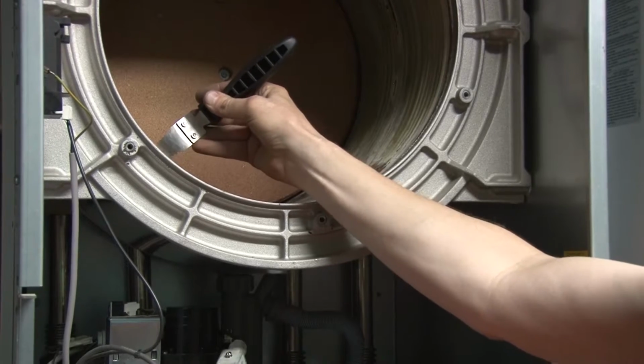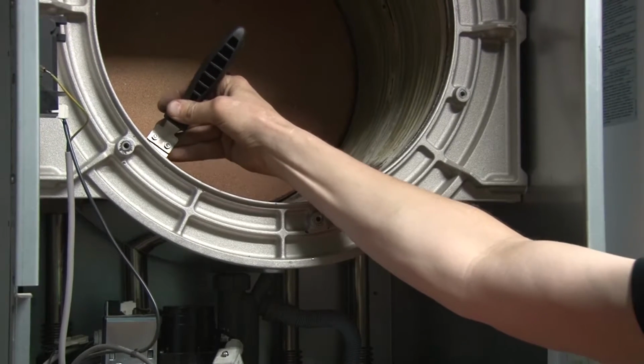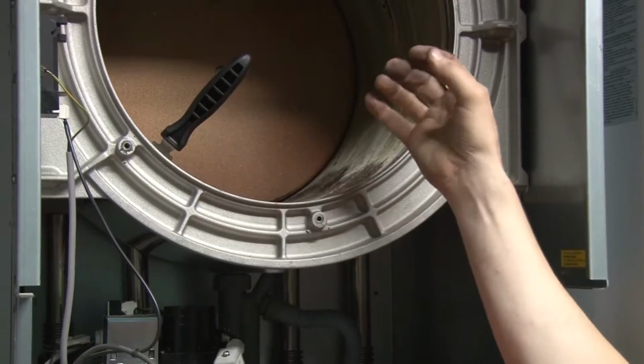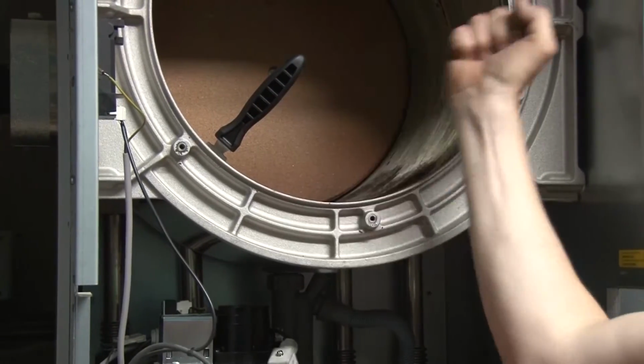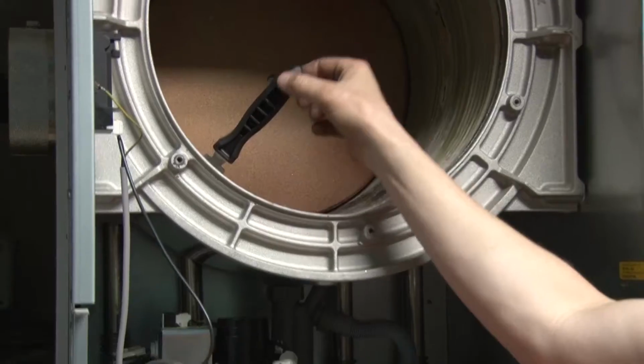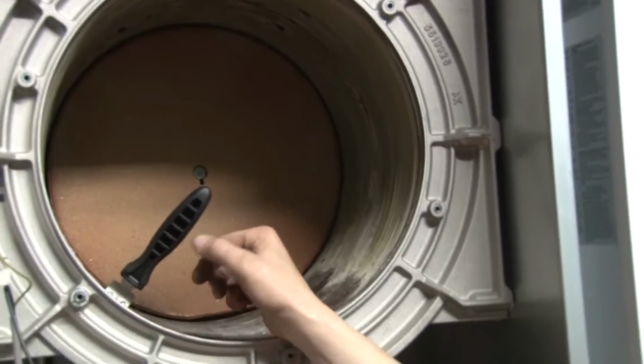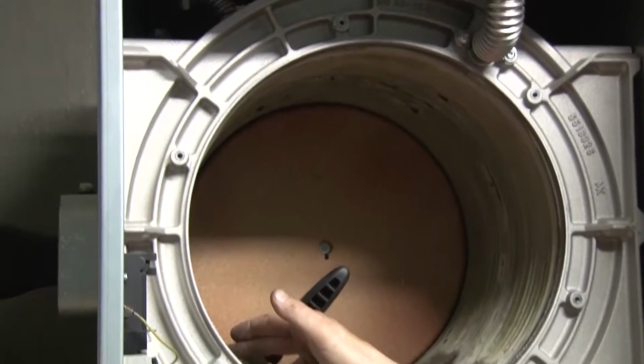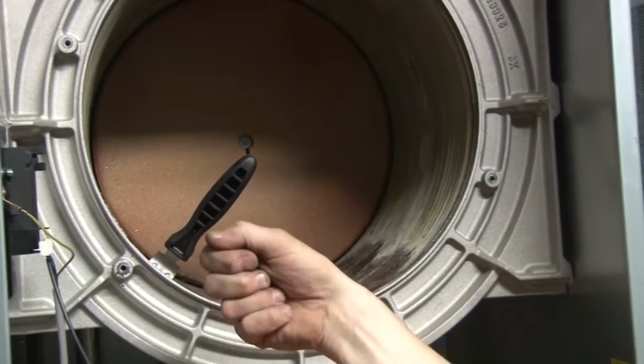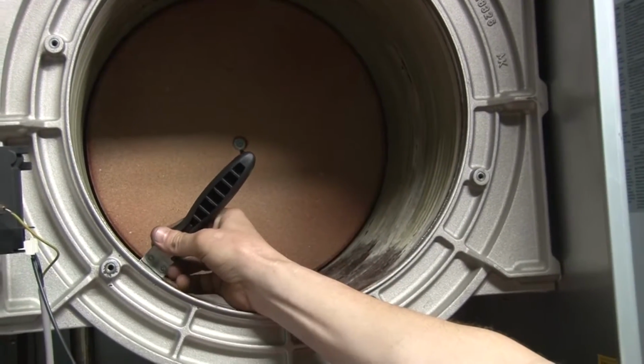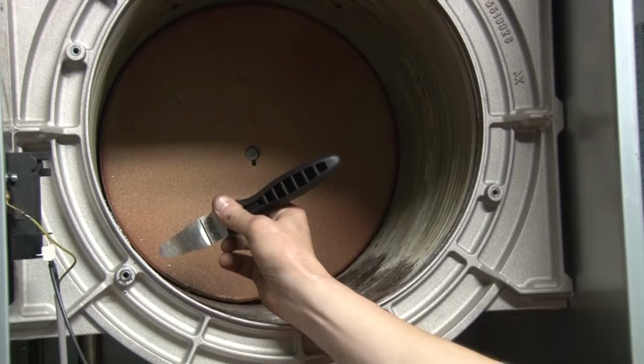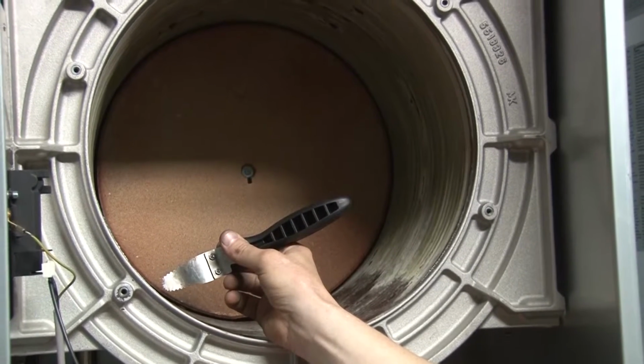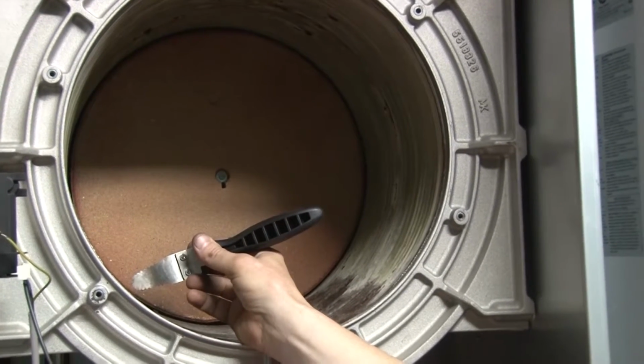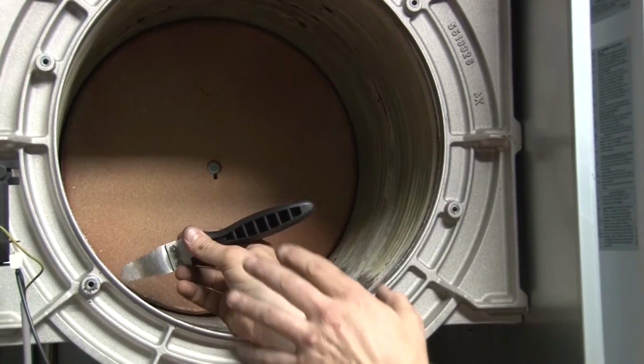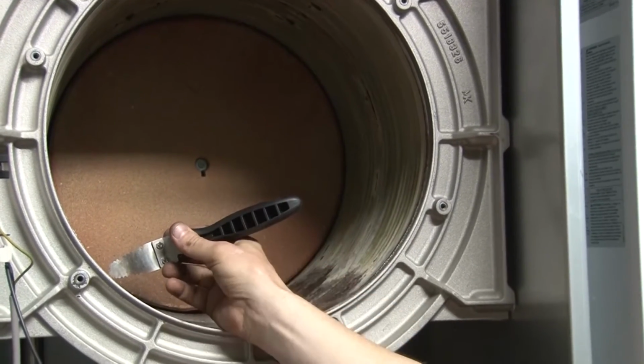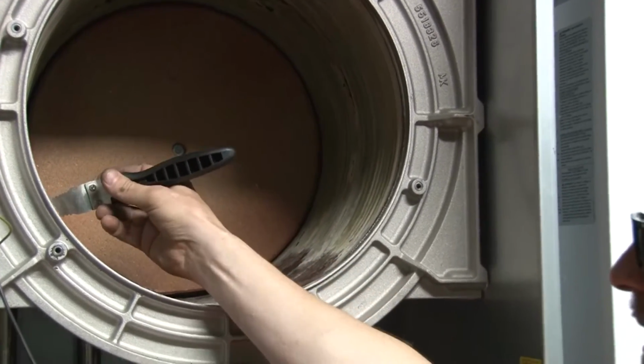See how that knife is not getting into those areas? I have to make sure I'm not going to take this knife and stab at the heat exchanger. The manual and the information that comes with this little cleaning tool say we don't want to gouge the heat exchanger. It's not made to scrape it. There are dimples that keep the gap consistent between the coils, so as the burner heats up and expands and contracts, those gaps are always at about a 0.8 millimeter distance from each other because of the dimples.